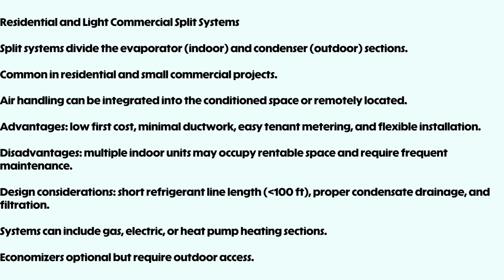They are simple, low cost, and ideal for small commercial or residential buildings. Typical configurations include one outdoor condensing unit serving one or more indoor air handlers. Advantages: low initial cost and flexible installation. Minimal ductwork required. Tenant-level metering and easy service access.